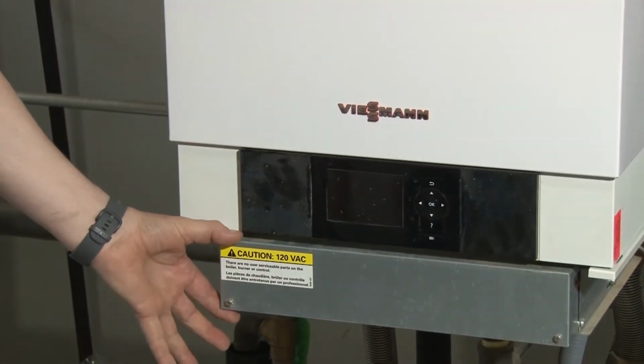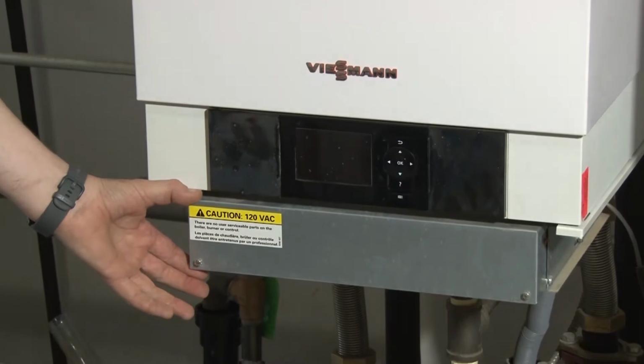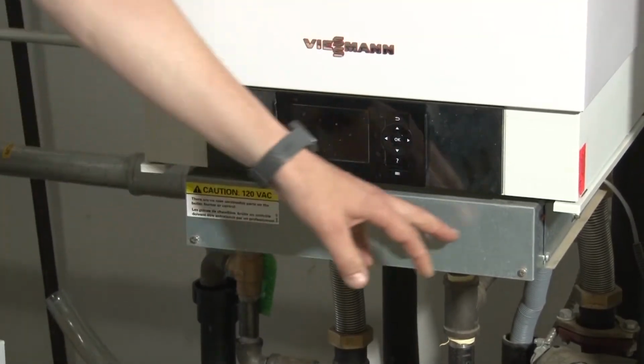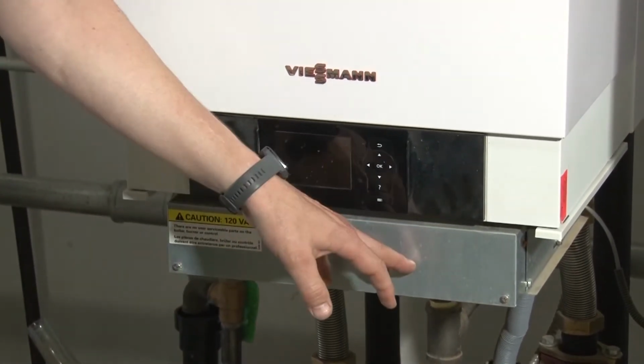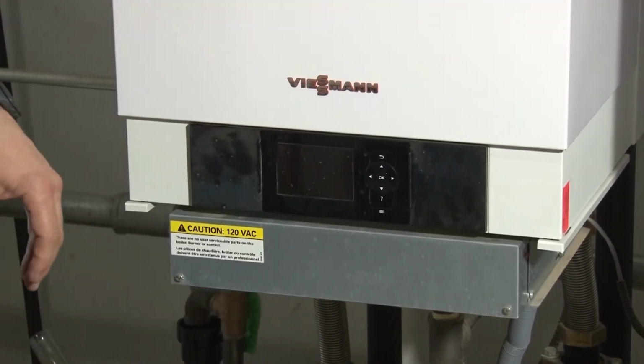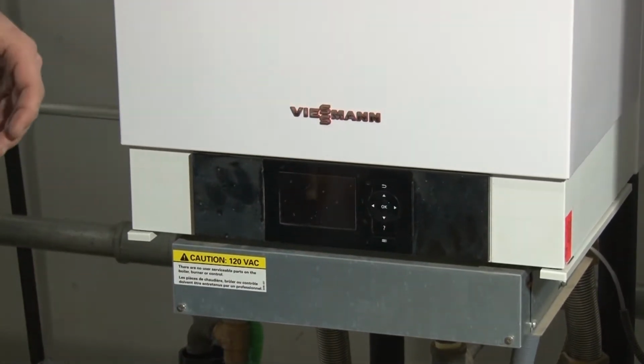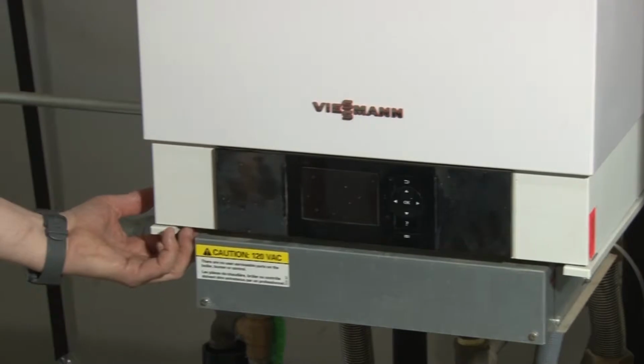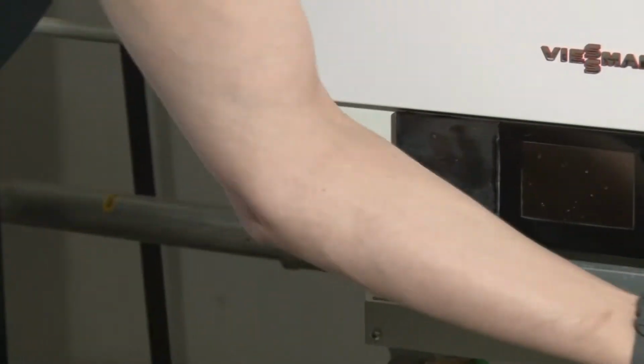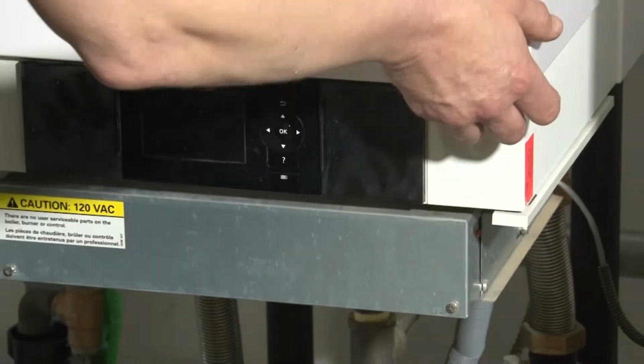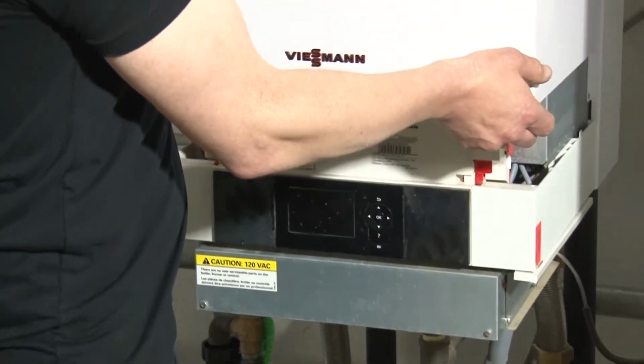Inside of here is all your wiring. So some factory wiring to the combustion controller. A lot of field wiring here, your pumps and stuff like that are all wired in here. We're not going to touch that today. It's more about troubleshooting and stuff like that. But inside of here, I would have a Phillips head screwdriver popped up in there, and I'd back those screws out so that I would be able to pop the door off. And I lift it up.